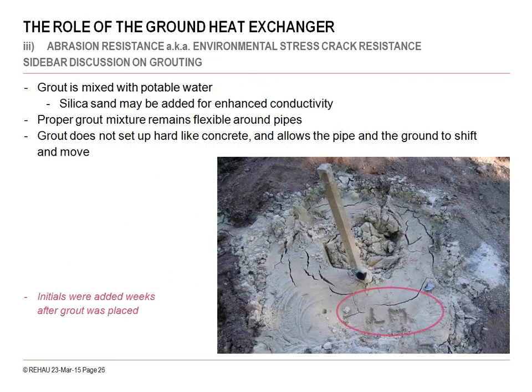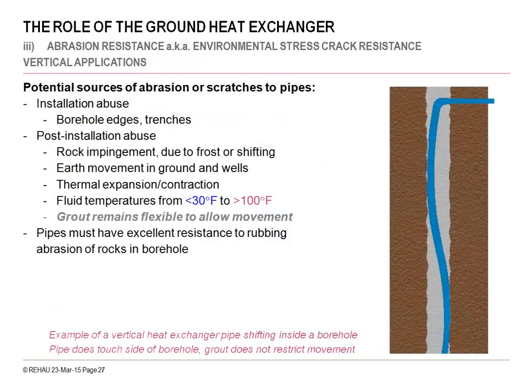Here's an image showing you grout after a few weeks, and you can see that it's still pliable, still moist. You don't want the grout to be drying out. That's why this bentonite clay, a special clay from Wyoming, is utilized. You can enhance the conductivity of the grout by mixing that bentonite clay in with silica sand. And with a higher conductivity grout, you can reduce the modeled borehole length for the project.